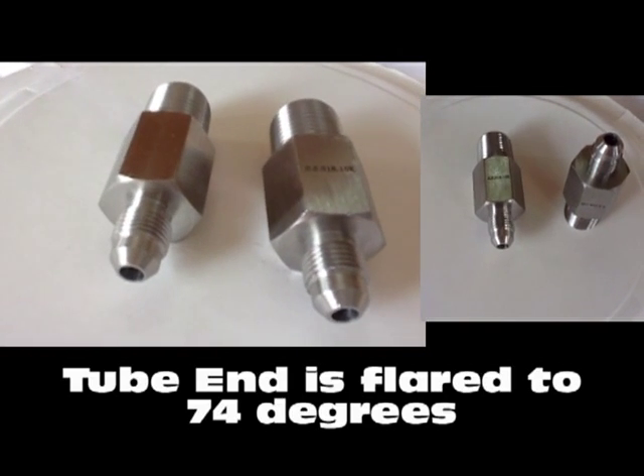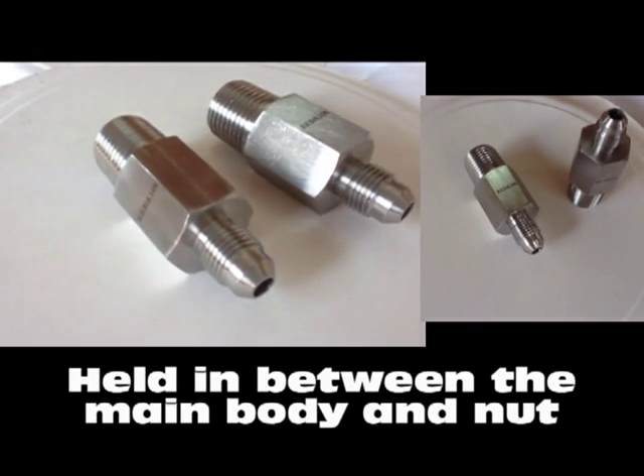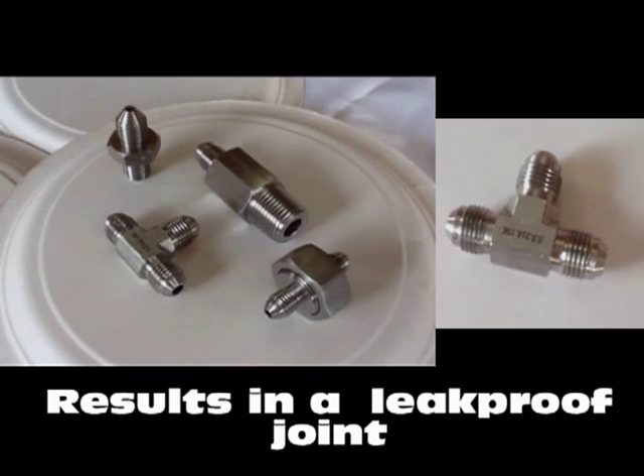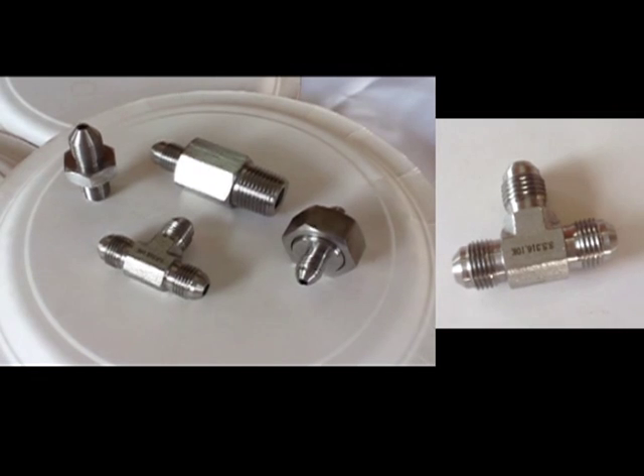JIC fittings are installed by making sure the tube end is flared to 74 degrees and held in between the main body nose and the sleeve nut. This results in a very effective leak proof joint which in turn allows full flow connection in the process tubing.